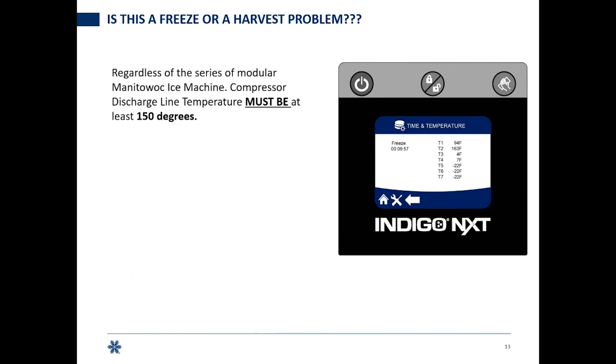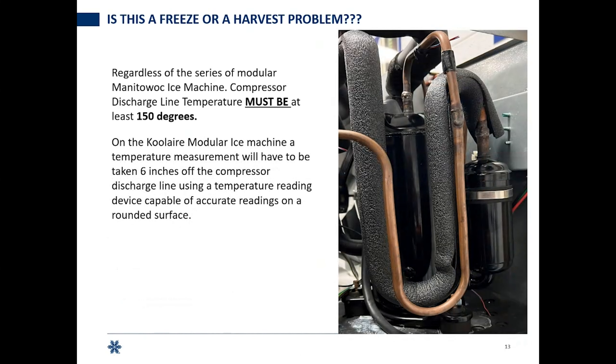Regardless of the series of modular Manitowoc or Koolaire ice machine, you've got to get above 150 degrees on your compressor discharge line. On this self-contained unit with the compressor inside, T2 is measured in your compressor discharge line. We're almost at 10 minutes in the freeze cycle and we've got 163 degrees, so we've satisfied that first requirement. On the Koolaire, you need something that can measure temperature on a rounded copper line — come six inches off that compressor and take a reading, since Koolaire doesn't have a display with thermistor temperatures.